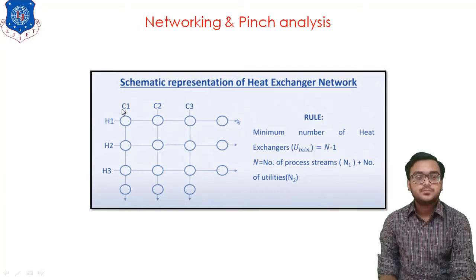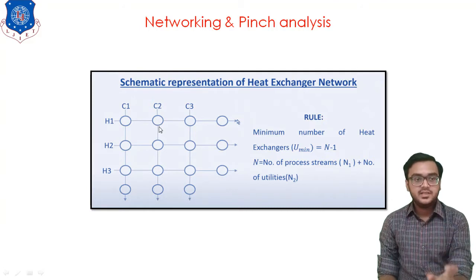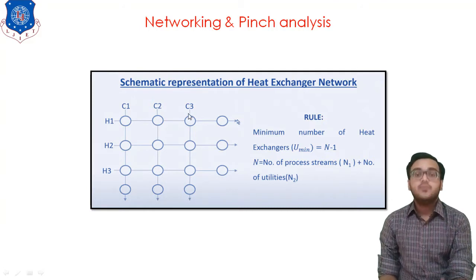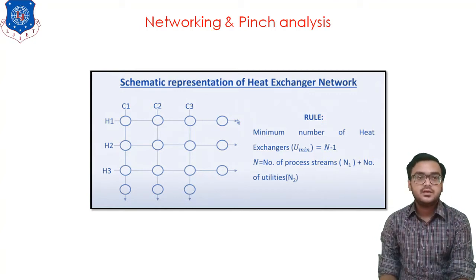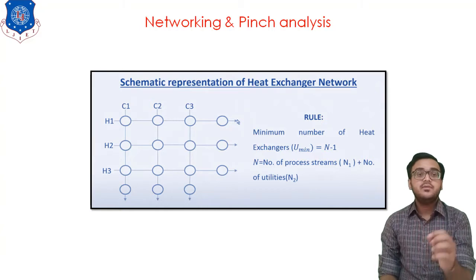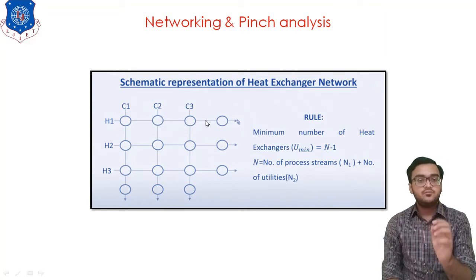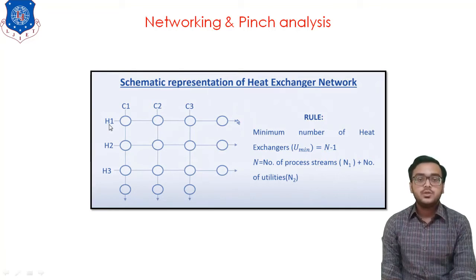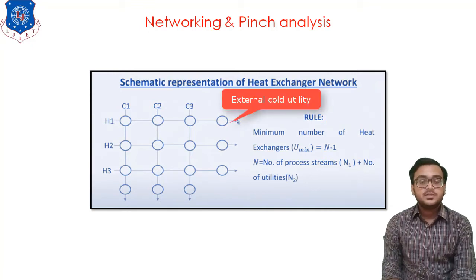H1 is initially flowing at 200 degrees and we want to reduce it to 100 degrees. After arranging the three cold streams over H1, at the outlet of C3 we have a fluid at 150 degrees. But we still want a temperature drop of 50 degrees. To achieve this 50-degree drop, we require one external utility — particularly a cold utility — to reduce temperature from 150 to 100 degrees. This is the external cold utility.